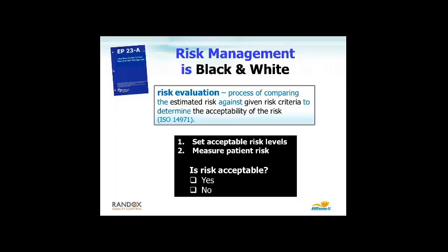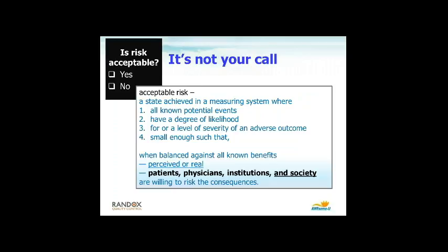Here's the trick though. It's not your call. That question, is risk acceptable, yes or no, belongs to these people now. Acceptable risk is defined as a state achieved in a measuring system where all known potential events have a degree of likelihood for a level of severity of an adverse outcome small enough such that, when balanced against all known benefits perceived or real, patients, physicians, institutions, and society are willing to risk the consequences.